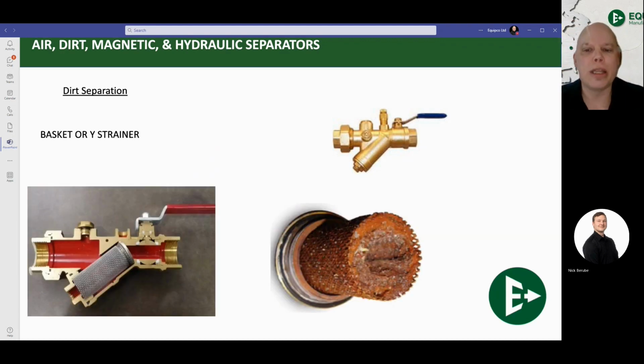You can use them. This is what's going to end up happening to them, on the right-hand side there. They're eventually going to get plugged and restrict flow back to the boiler, causing a no-flow situation, and there's going to be an error code. If you do use them, please clean them. There is a place and a time for them, but I'm just not a huge fan myself because there is so much better.